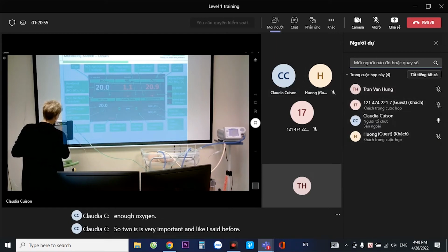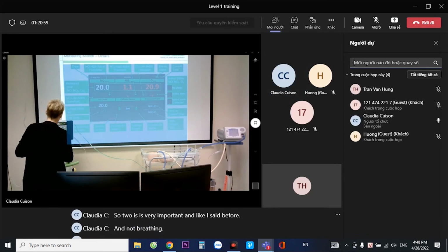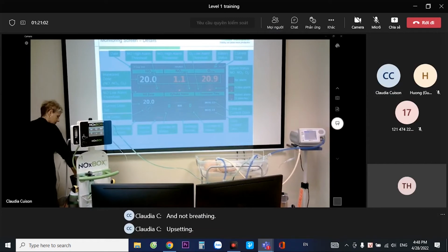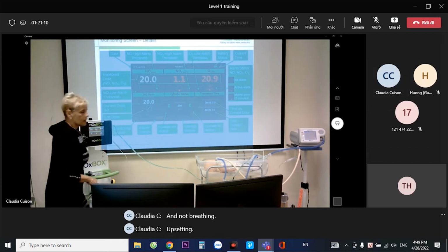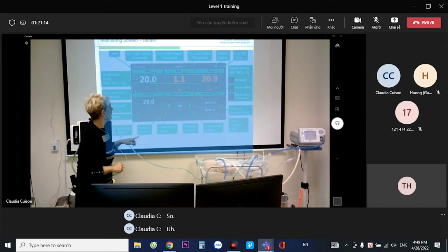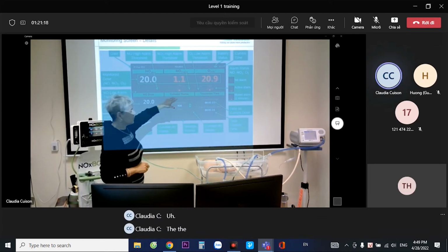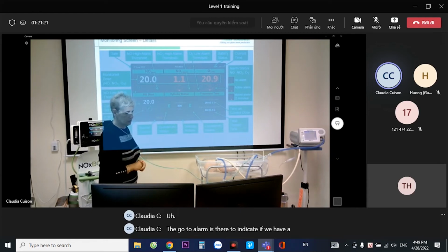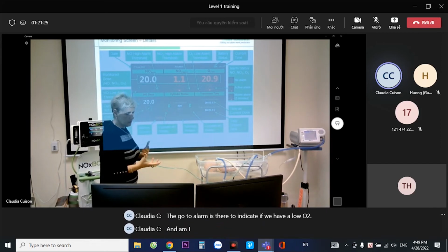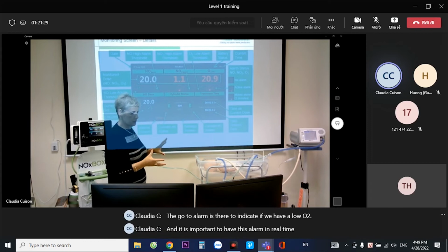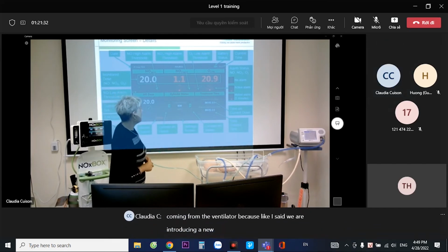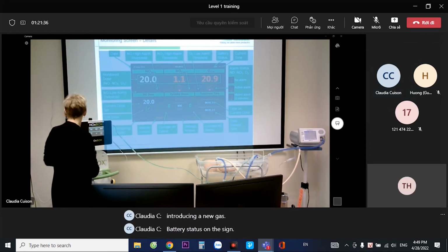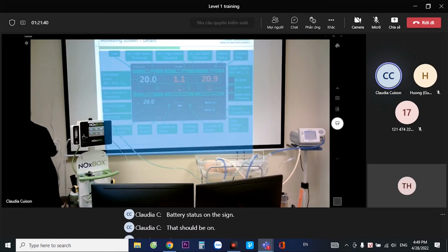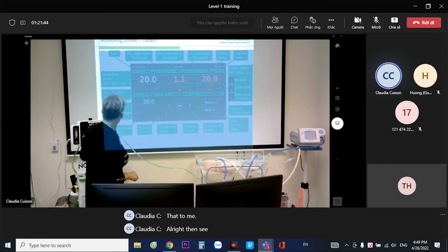I hope you can see the screen. So, a couple of important points here. Like I said, the top level is a real-time reading of NO, NO2, and O2. The alarm thresholds are below the readings. To change an individual alarm, simply press the respective pencil or arrow button above the alarm value. You can also mute the alarms. There's a mute symbol there. You can press that to mute it, and it will last about 2 minutes.